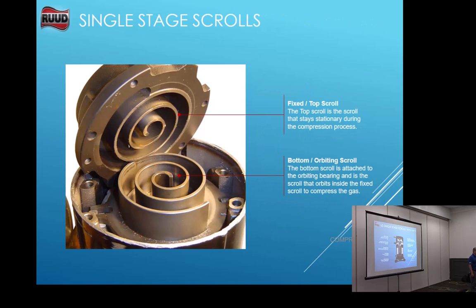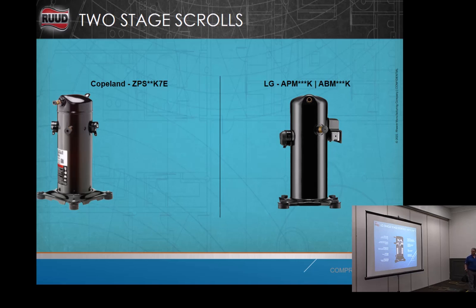The two-stage scroll compressors, the difference in the Copeland and the LG is the Copeland has an internal DC solenoid, okay? We get 24 volts coming from the control board to this plug on the side of the compressor, to a rectifier. And it converts that AC signal to a DC signal into that solenoid. The calls that I get on the Copeland side is, hey, Mike, when it goes into high stage, it pops the fuse. Okay? Pull the plug off the side of that compressor, have the power off. Go get your ohm meter, ohm it to ground. If the solenoid ohms good, it's more than likely the plug going to that compressor. Look at it further. If you look in the side there, you may see some rust streaks on the compressor and in the plug itself. That tells me that moisture has gotten in there. Has it gotten in there from rain?